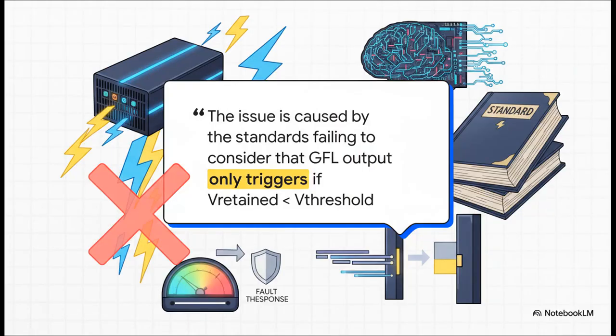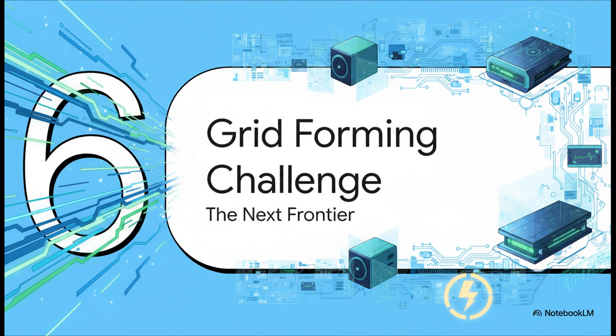So to boil it all down, and this is a quote straight from the research, the entire problem is caused by the standards completely failing to consider that a grid-following inverter's fault response is conditional. It's not always on. It only kicks in if the retained voltage drops below that critical threshold. Simple as that.